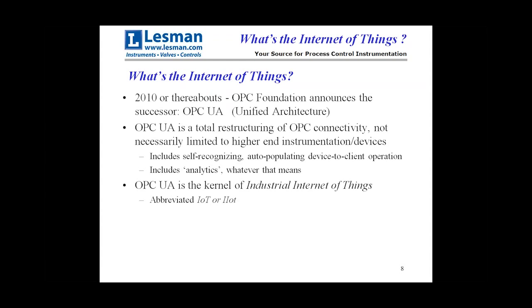Back around 2010, the OPC Foundation announced the successor to OPC DA called OPC UA — Unified Architecture — which totally restructured OPC. It would self-recognize objects out there, auto-populate the dreaded tag database, remain a server-client operation, and include analytics such as alarm notifications. OPC UA is the kernel of what people call the Industrial Internet of Things, abbreviated IIoT. So when you see IoT in the trade journals, now you have some idea what that is.